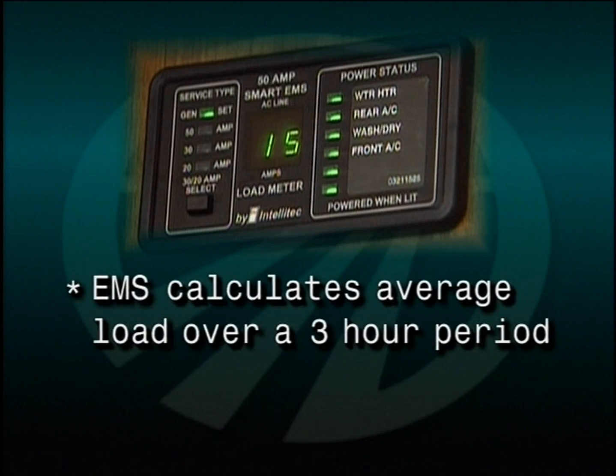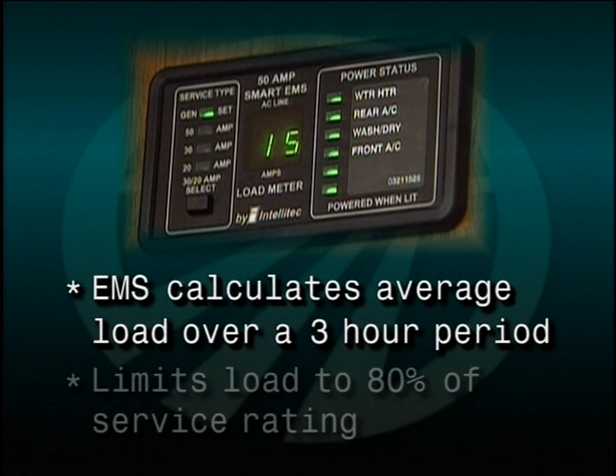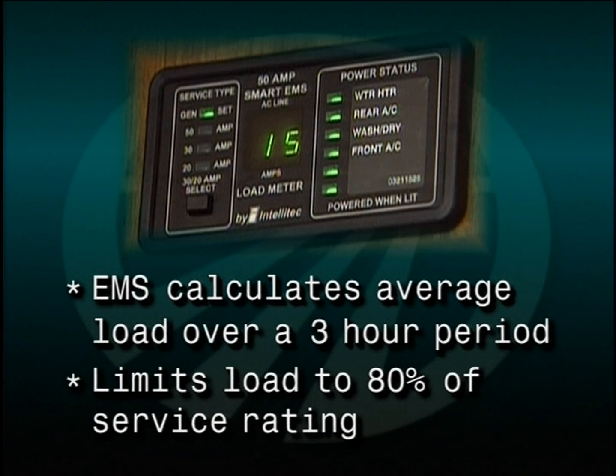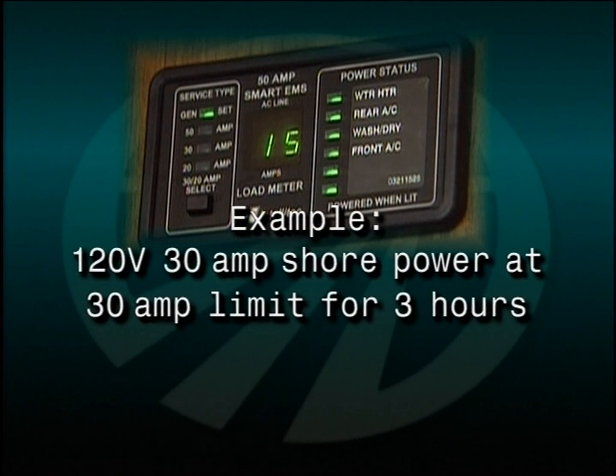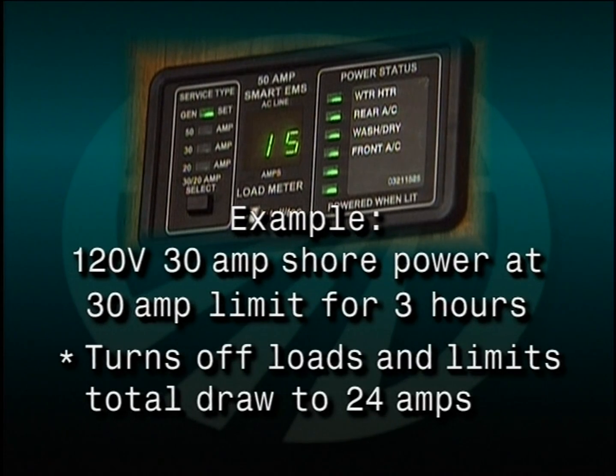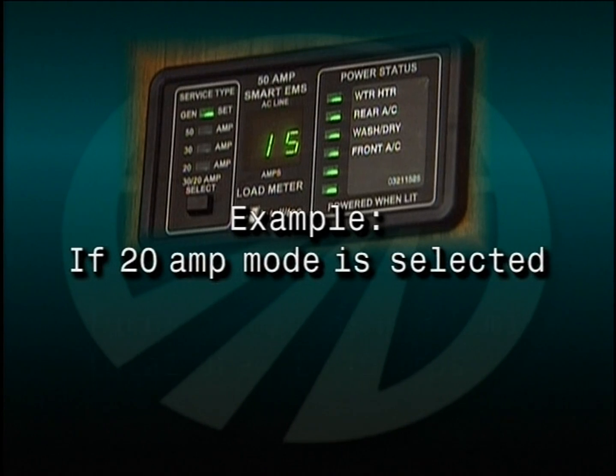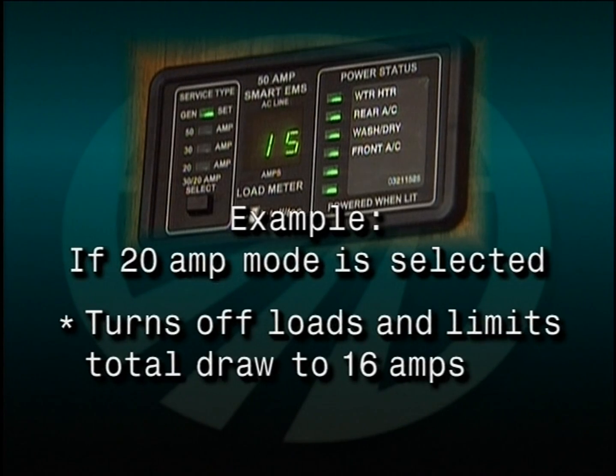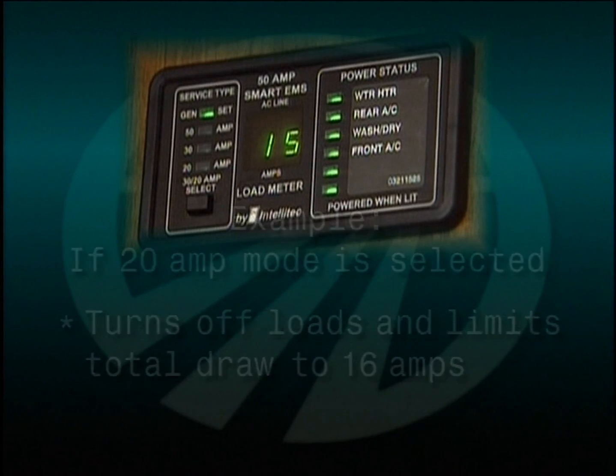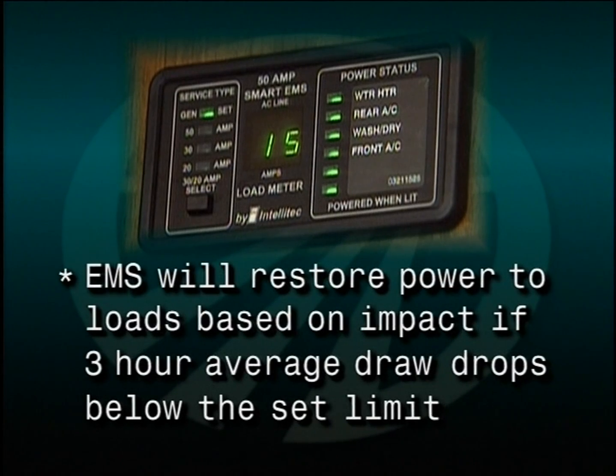The EMS calculates the average load over a 3-hour period and limits the load to 80% of the service rating. For example, if a system operating under 120 volt 30 amp service has been running at the 30 amp limit for 3 hours, the EMS will change its shedding threshold to 24 amps and turn off loads until the 24 amp limit is attained. If you select the 20 amp mode, this limit will translate to 16 amps. Because the EMS calculates a running 3-hour average, if the average load drops below the limit, the system will restore power to loads based on their impact on the limit.